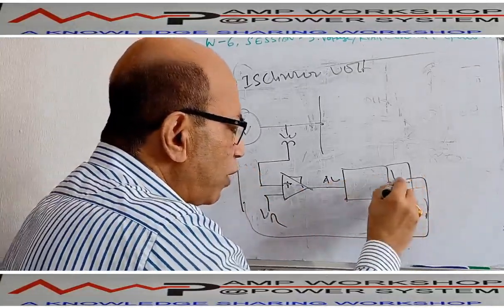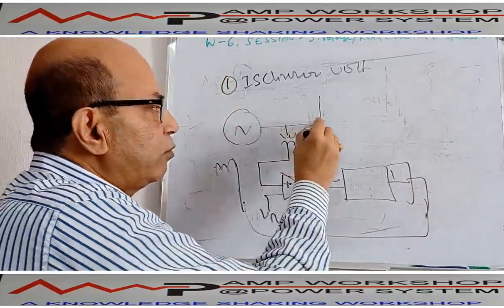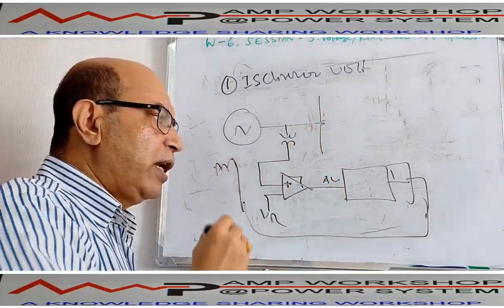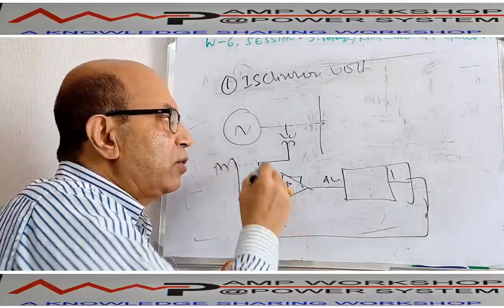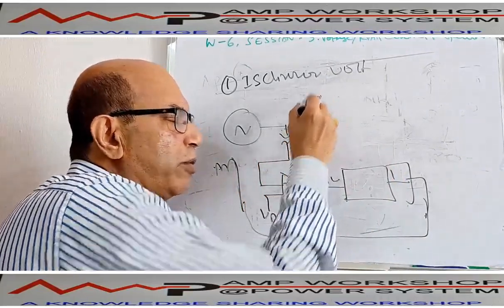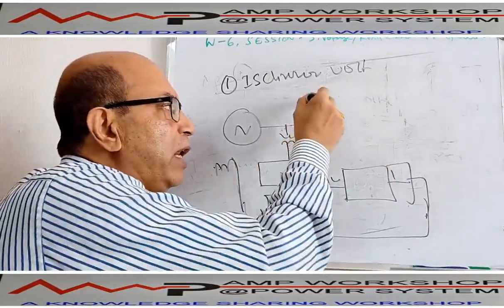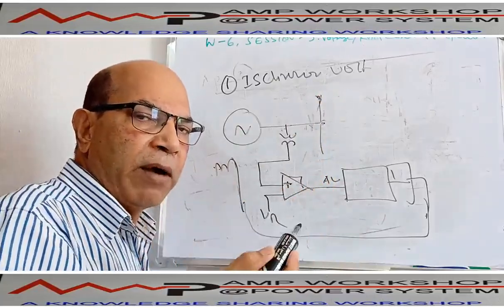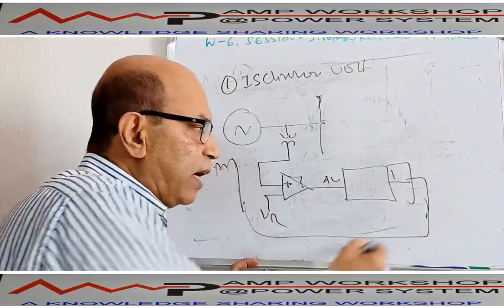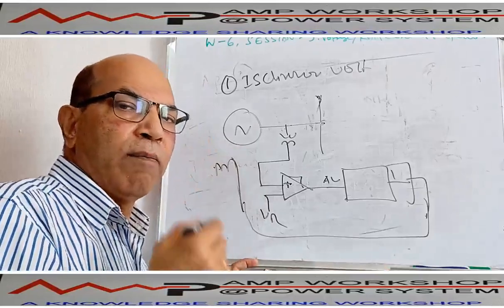As the voltage goes down, it will give more and more excitation, so the voltage keeps rising. It will happen instantly, so you will not see a change of voltage here. If there is a minor change, it will automatically come back. You don't need any manual intervention. If the machine is running in this way, you call it isochronous voltage mode.